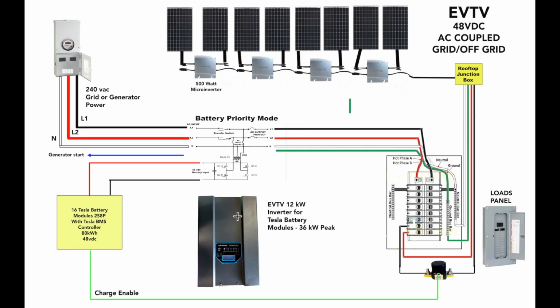38.65 volts as being a low voltage cutoff, where this will switch over, and we can start charging our batteries from the grid or the generator, and we have a generator start signal to start that. We don't really ever want to do that. We want to operate in a band where, in battery priority mode, we're using the batteries. And our output goes to the loads panel.